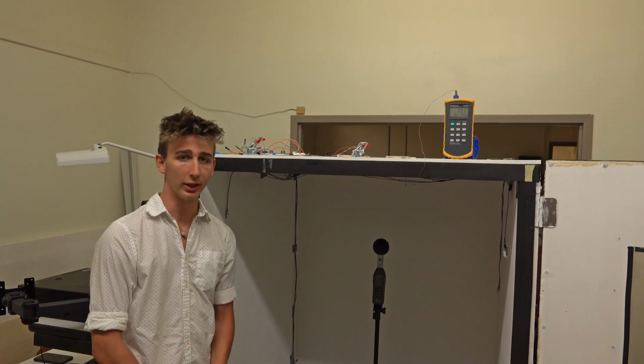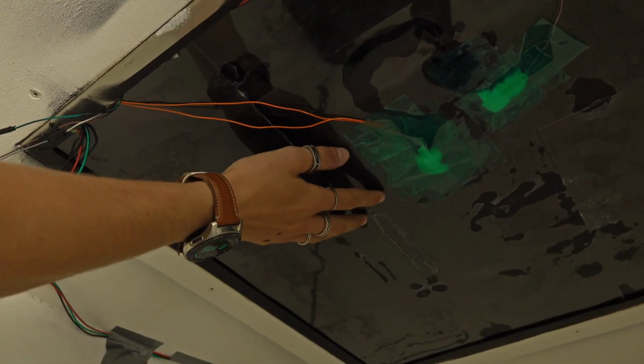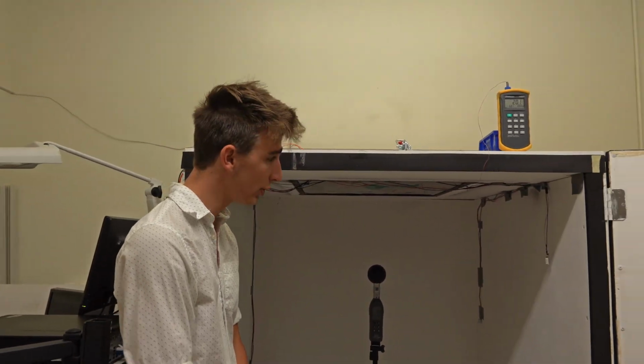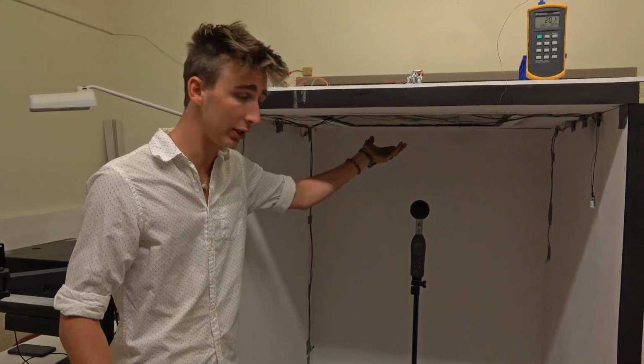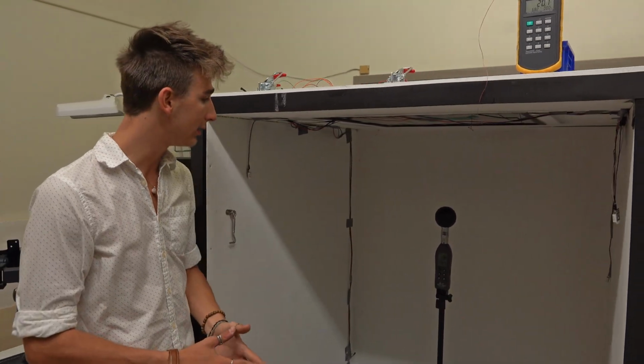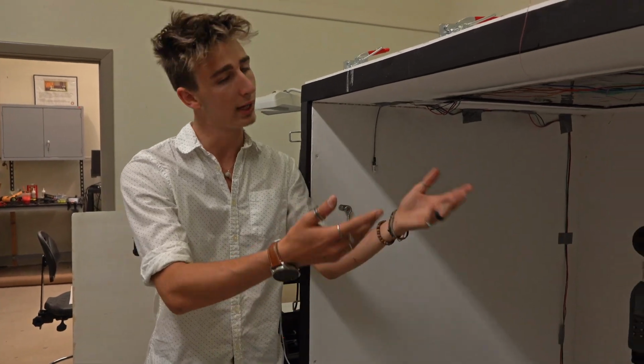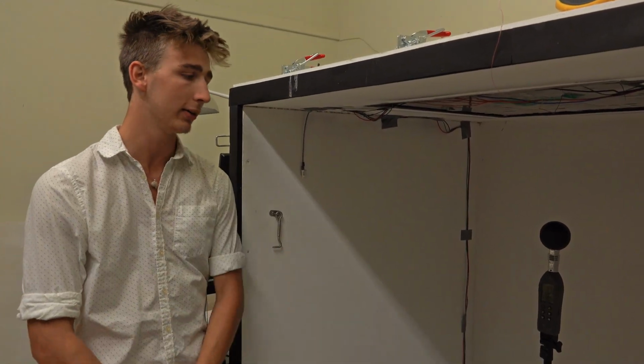Some benefits of radiative cooling are that the system has no airflow. Essentially, this plate becomes extremely cold, and for anyone in the room, the heat from their body will radiate towards the cold plate. So that, as stated before, has no moving air, and it can also be a completely modular system. In a building, you could have this ceiling tile across several square meters of the ceiling, and if there are people underneath a section, then only that tile could be operated. But if people move to another section, then that tile could operate, and that would save a lot of energy because only the tile where people are is operating.